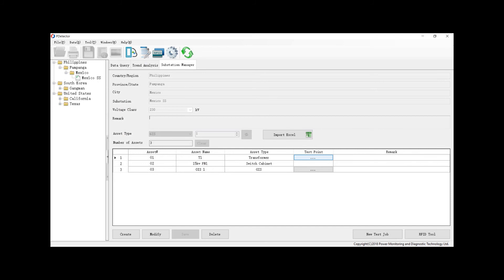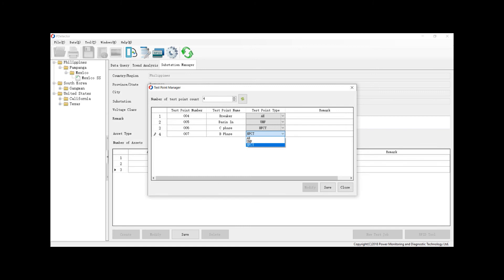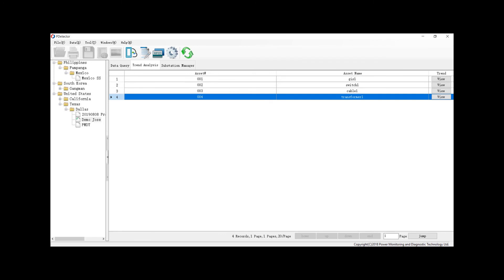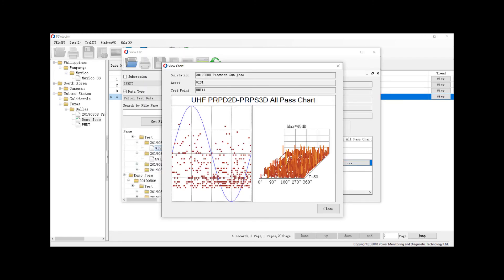PMDT has developed ways to improve test efficiency and condition-based asset management by implementing the routine patrol and RFID patrol functions. The intelligent routine patrol is used for more efficient online partial discharge testing. It allows users the ability to create new test jobs with all test points in a template on the PC-based software. The test job will then be sent to the P-Detector main unit and the user will proceed to survey the power equipment and collect data for pre-set test points. The data will be saved onboard the main unit, then uploaded to the P-Detector PC-based software.